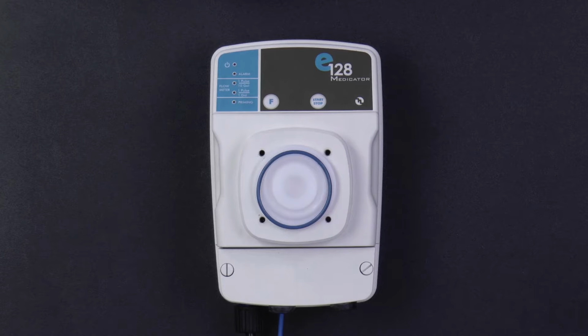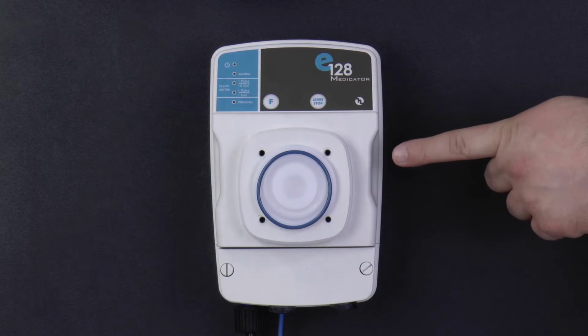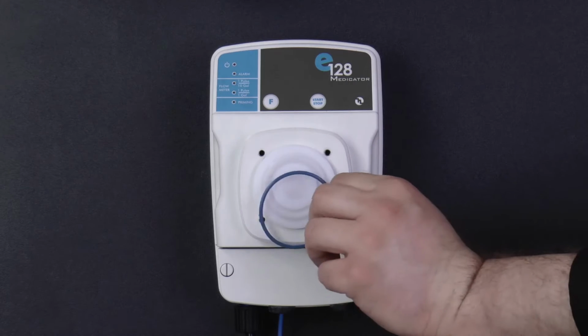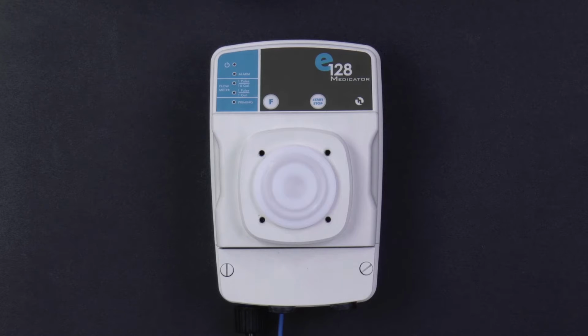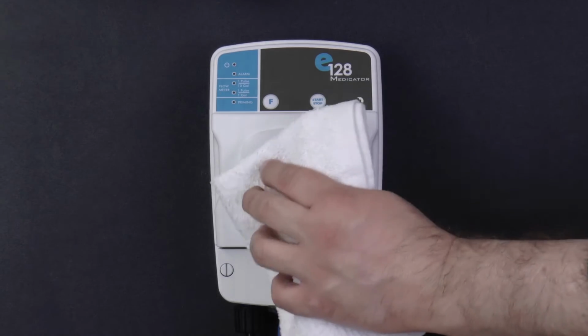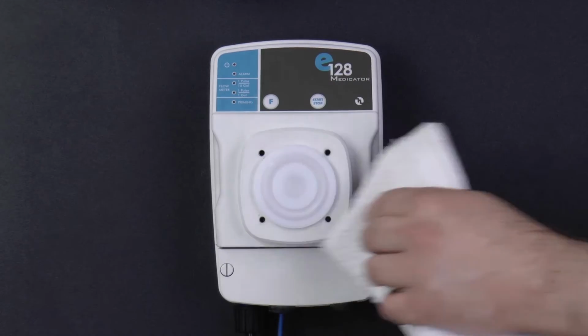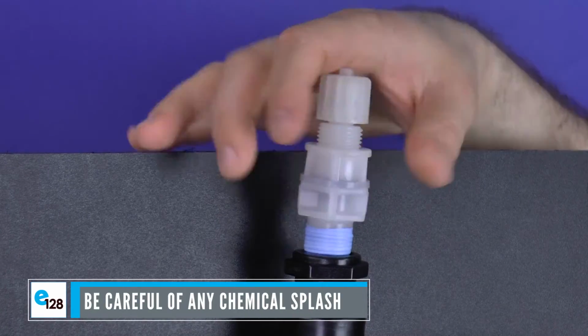If the blue O-ring is not there, still discard the pump head, but check to see if the blue O-ring is stuck to the E128 pump. If so, remove and discard the blue O-ring now. This can be done with your finger or flat blade screwdriver. Using the small towel, wipe clean the diaphragm and any other chemical-stricken parts on the pump. Unscrew and disconnect the old injection valve from the T.